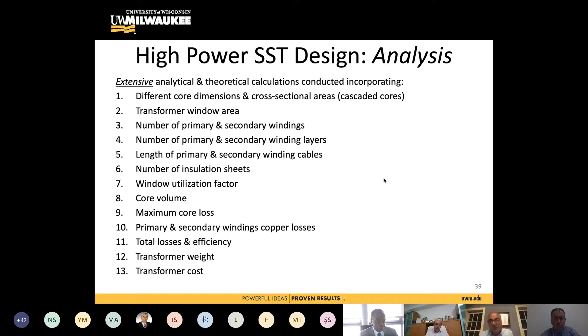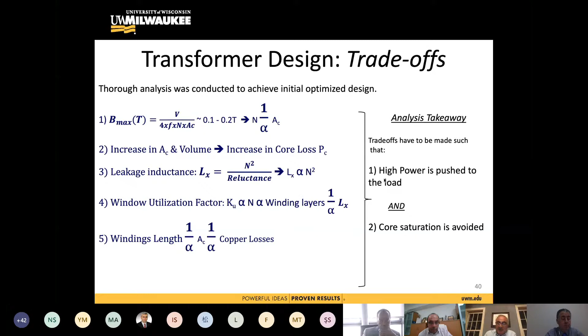The high frequency transformer sits right in the middle, and you have a lot of trade-offs. Your Bmax is generally limited based on the materials you use; for instance, for ferrite, you cannot go beyond 0.3 Tesla for the core. Then you don't want to increase the volume too much, because if you increase volume your loss goes down, but your weight and cost go up. Leakage is limited based on the number of turns, which impacts your winding length and loss in the system as well.